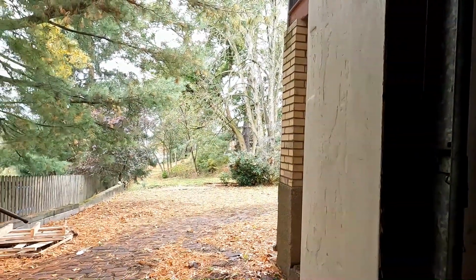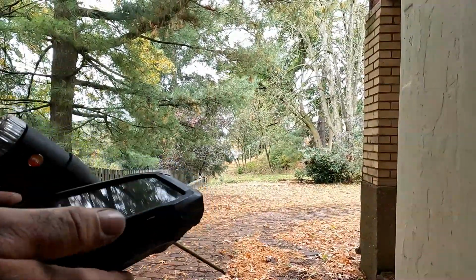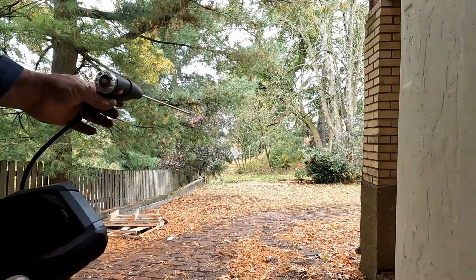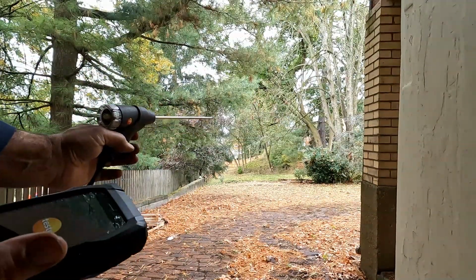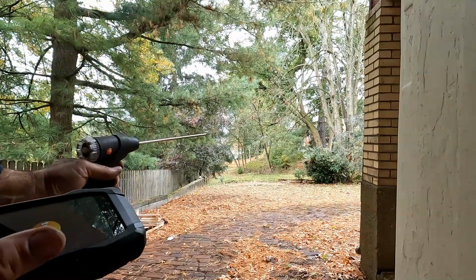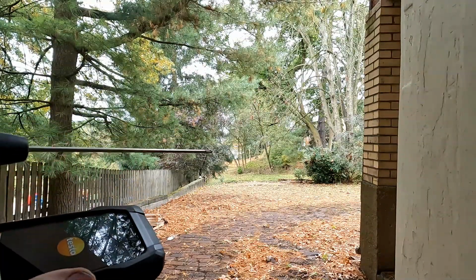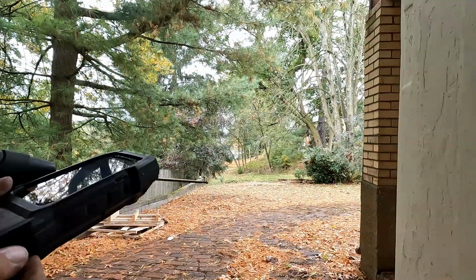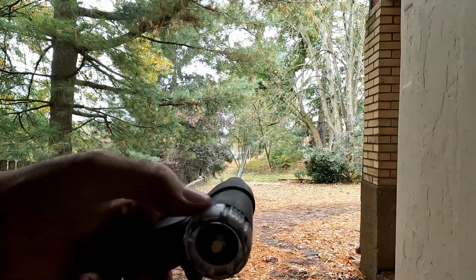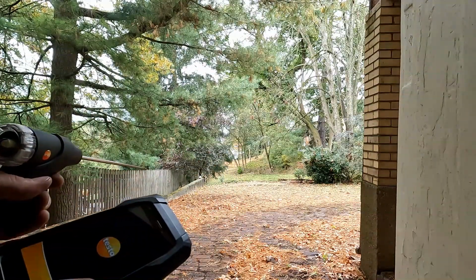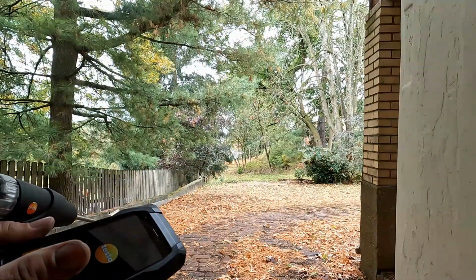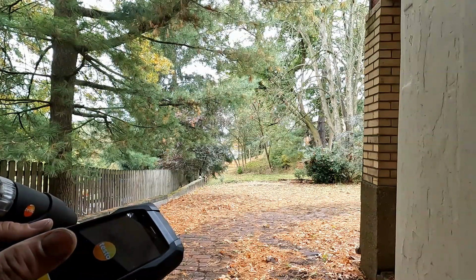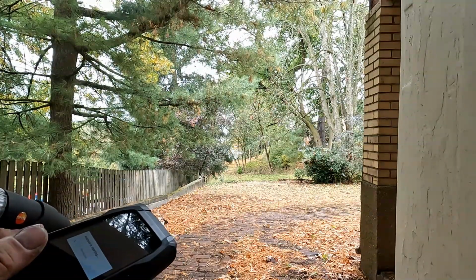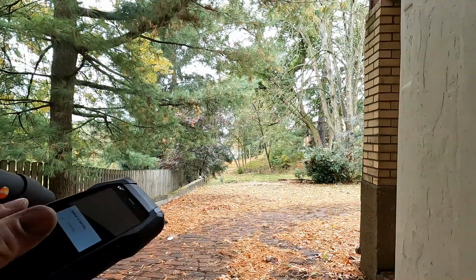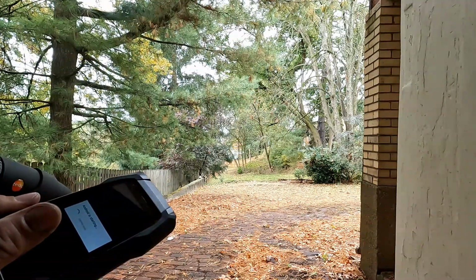So this is the Testo 300. Can you see this? It tells you specifically that this gets started in fresh air for the reason to clean any of the CO remaining. After you shut this off, you drain the trap and you clean this, blow the water out of this. You do not start a combustion analyzer in a basement with indoor air. It gets started in the fresh air. The only reason that guy's doing that is because he watched the guy in Massachusetts.